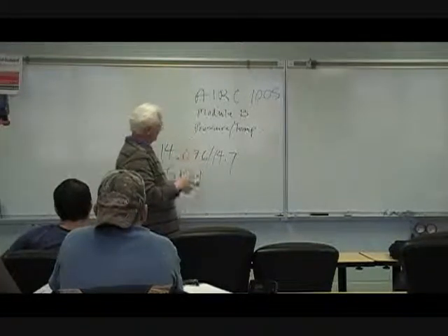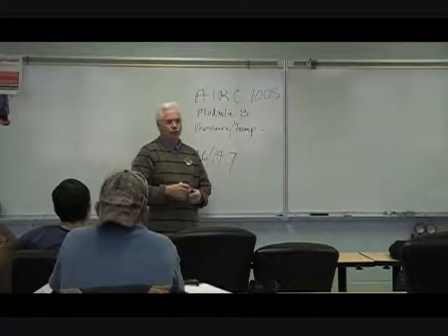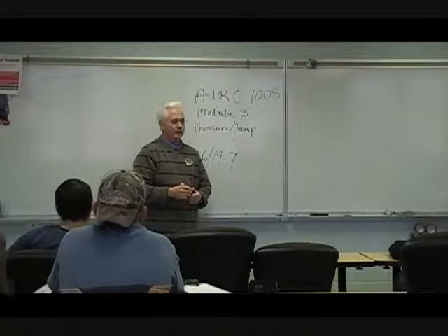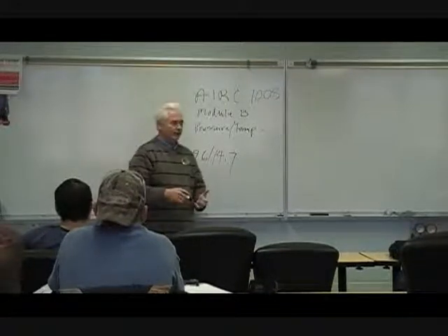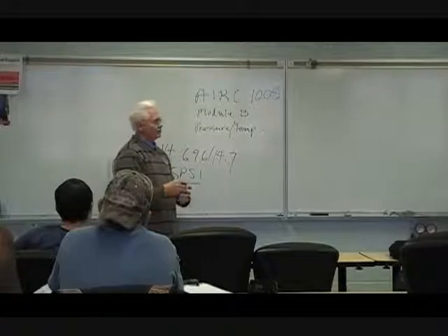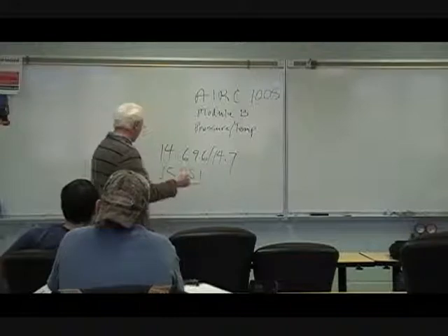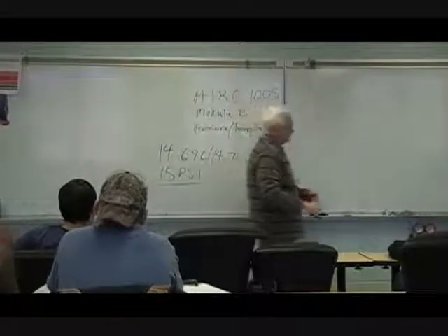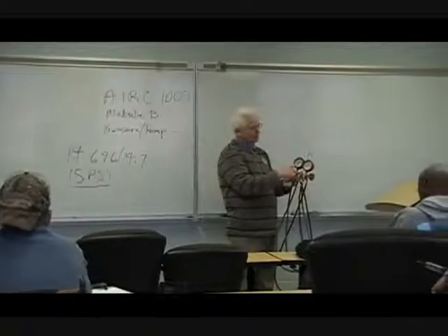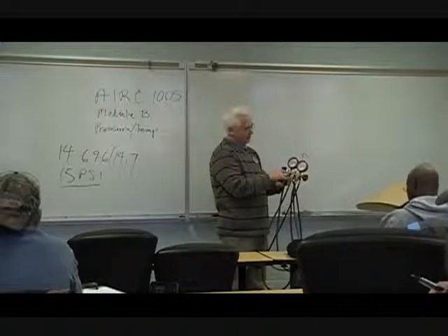Everything we talk about in this class is going to involve the air conditioning system or refrigeration systems in some way. It's going to involve the pressure-temperature relationship. If you're doing scientific equations dealing with pressures, it always asks you to determine absolute pressure. When we install our gauges on a unit, we're going to be reading gauge pressure. We've got your low side pressure gauge and your high side pressure gauge. When we connect these gauges to a system and read our pressures, we're reading what's known as gauge pressure.